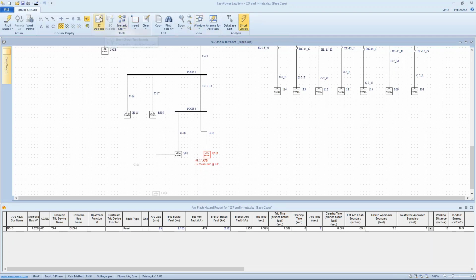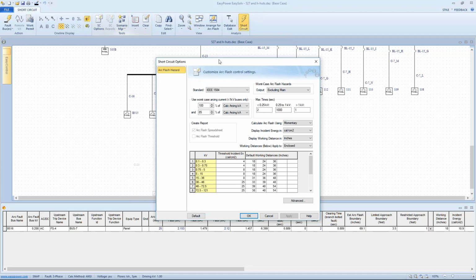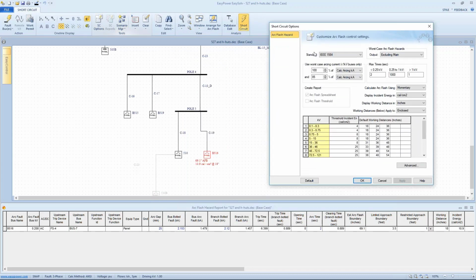In short circuit, we go to short circuit options. Here we find the arc flash hazard tab. These are the tweaks, if you will, that the IEEE 1584 model allows. First of all, it's automatically comparing 100% arcing current with 85% arcing current. In this case, we're excluding the main of the panel, so whether or not it looks like we have a breaker set up, it's being excluded, and we're relying on the fuse to trip the arc fault.